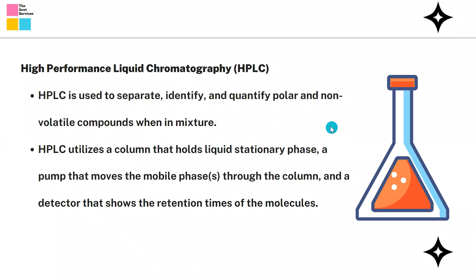This is where the solvent is stored. When it is pumped through the HPLC tube, it acts as a moving agent, and the HPLC tube acts as the stationary agent. When the sample is injected here, the solvent takes it along to the HPLC tube. In this tube, the sample gets separated according to its different parameters, and then it is detected here. Again, the detection comes in the form of peaks, which can be identified with the standard sheet provided by the company.